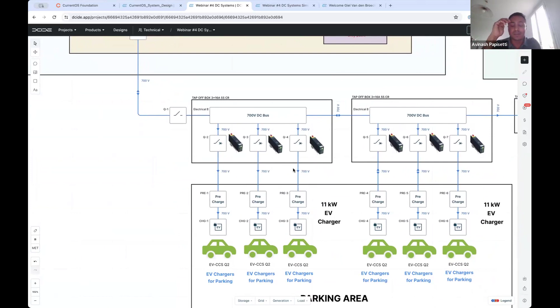Now, this product doesn't have an external energy management system. Each and every load and source is actually running on something called droop control. Droop control is pretty well known to a lot of institutes and companies doing research on DC. Just by sensing this, the bus is at 700 volts, but as I said, voltage need not be a fixed number, it could be within a bandwidth.